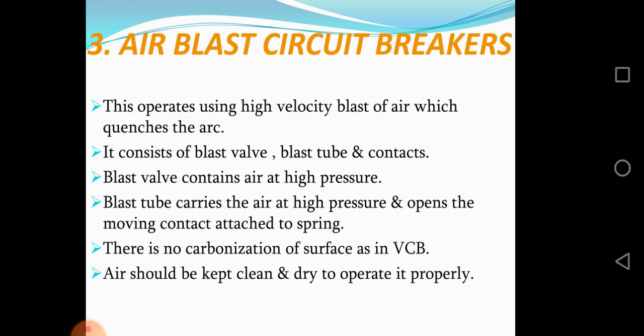The third type is the air blast circuit breaker. This operates using a high velocity blast of air which quenches the arc. It consists of a blast valve, blast tube, and contacts. The blast valve contains air at high pressure; the blast tube carries air at high pressure and opens the moving contact attached to a spring. There is no carbonization of surface as in a vacuum circuit breaker.